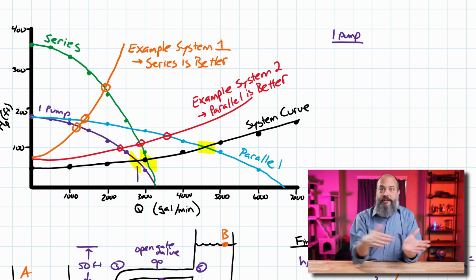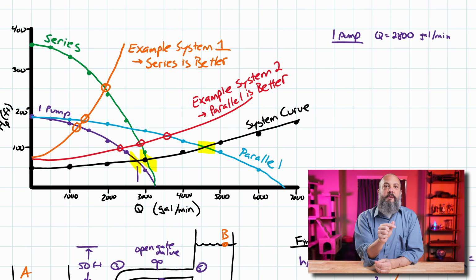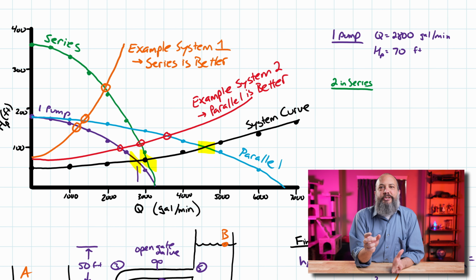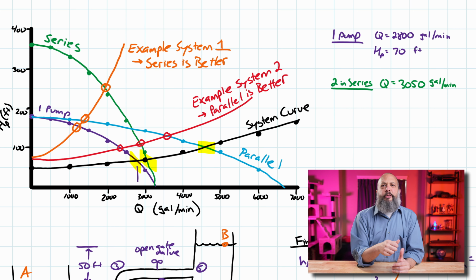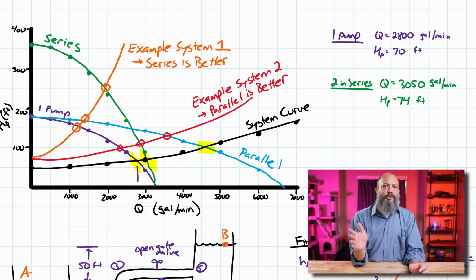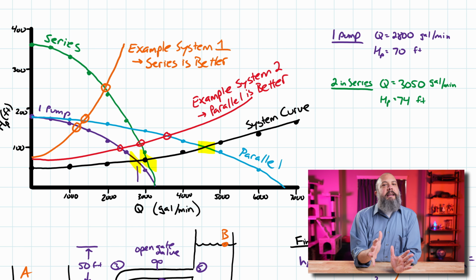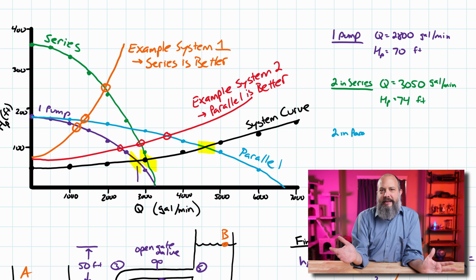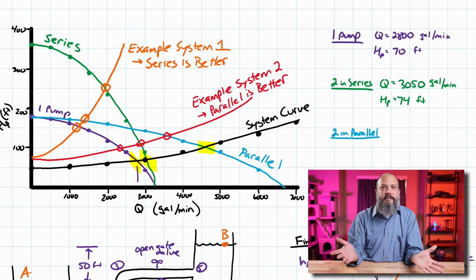Because this is a very shallow, flat curve, you can see that the one pump and the series conditions are almost next to each other. Going from 2,800 gallons per minute with one pump, we'd only increase to about 3,000 gallons per minute by adding a second pump in series. So this would really be a waste of money to add an extra pump in series. You get hardly any extra performance, maybe 10% extra performance for double the cost.